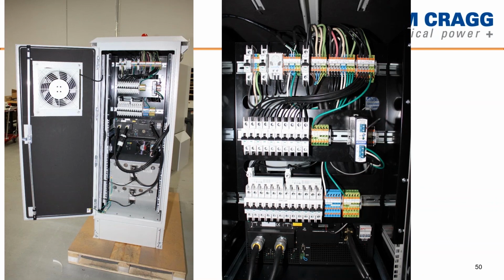So on the top section, we have about 8 120 volt single pole breakers. And at the bottom, we have 208 volt single phase breakers, all connected with Eaton breakers with custom bus bar distribution across each of the breakers. One neat thing about this is we included a contact relay card onto the UPS, which if there was a utility failure and we went on battery, it would initiate the strobe red flasher on top of the enclosure. So at any given time, you can look out at the installations and see if there's an issue with the system.